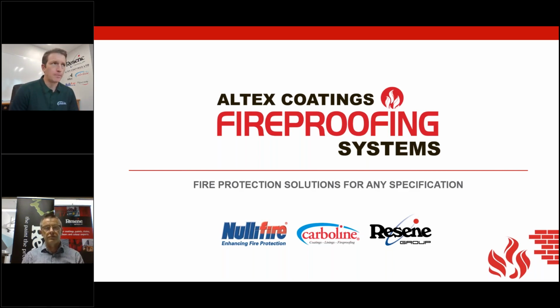Unlike your initial shop application where your surface preparation has to be abrasive blasting, more than likely, for your liquid applied intumescence, on site for repair, site damage, transportation, erection damage, all those materials can be repaired by power tool cleaning. A couple of different standards, the SP3 and SP11 are typical, depending on the level of corrosivity that you're facing. Reinstate the priming system, or a priming system that's appropriate for the environment, zinc or an epoxy type materials usually. Reinstate the intumescent coating within that area, lapping up the area of damage which has been feathered in, and then re-top coating over the top of that particular material. So yeah, that's easily done.